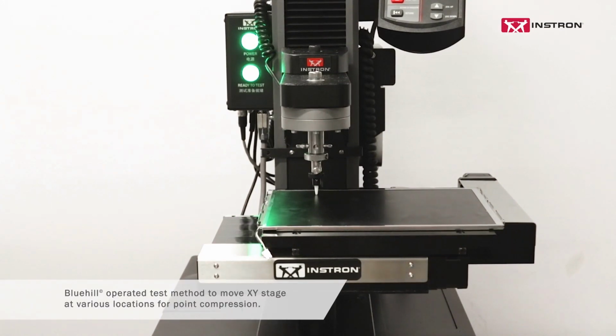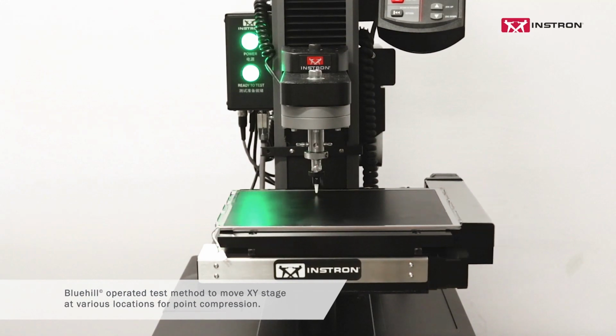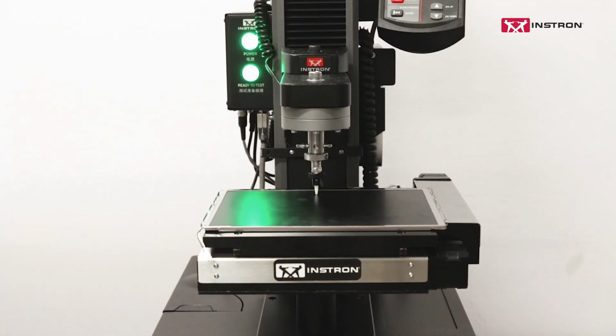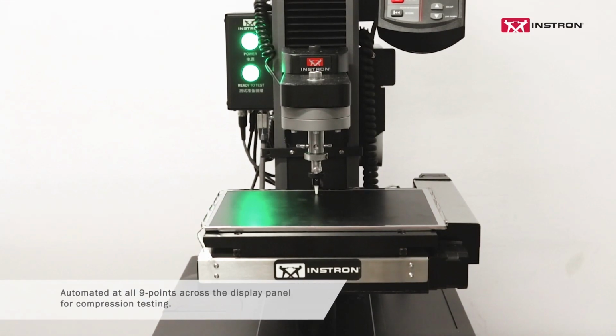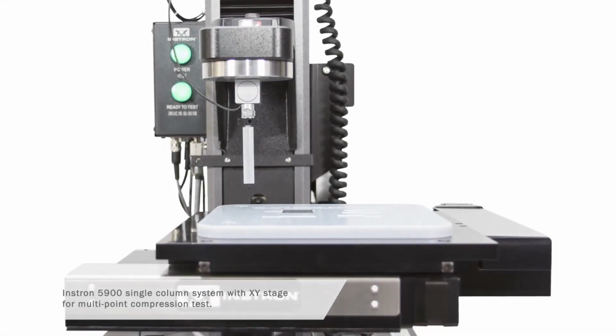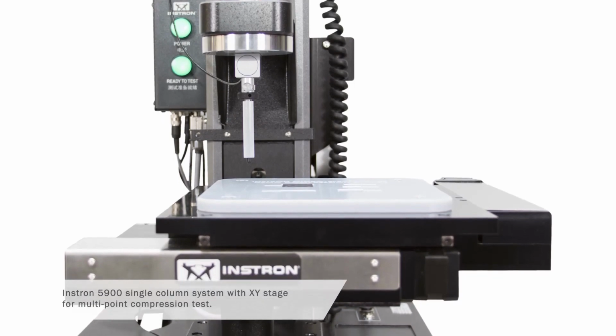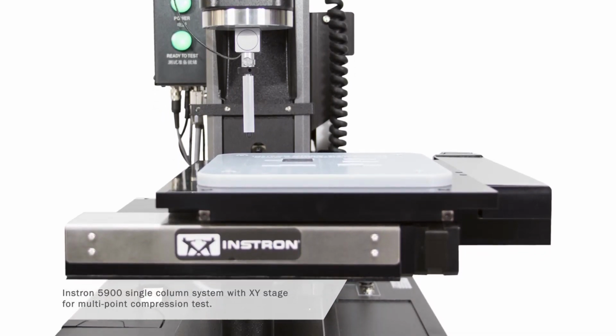This one shows a compressive load that's being applied at 9 different locations around the screen. And this is to simulate loads that it might see in use when somebody is tapping at the screen to take different actions. And this last one shows an integrated circuit test.